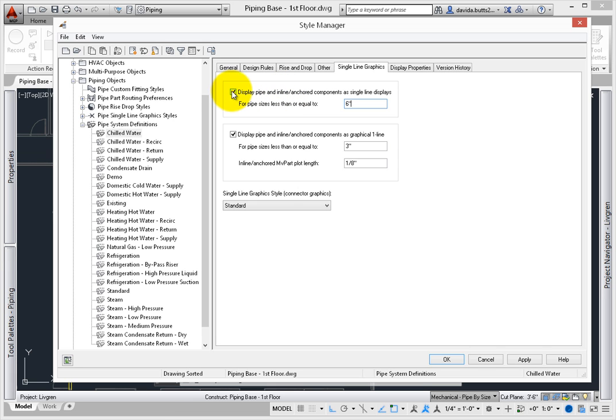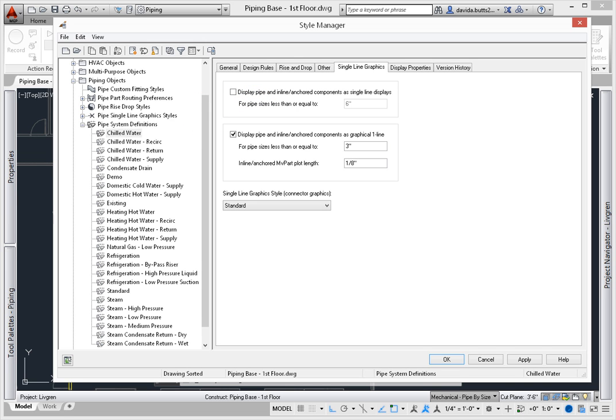Anything above 6 inches is shown as a double line. Set the graphical 1 line to use 3 inches as the top size for sizes less than or equal to. Deselect the single line display so that any pipe bigger than 3 inches will show as a double line.